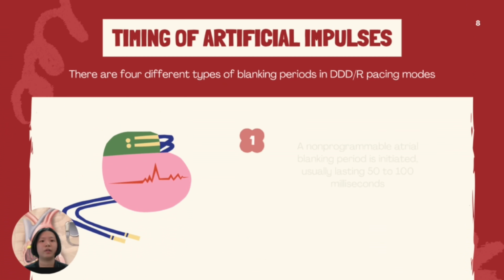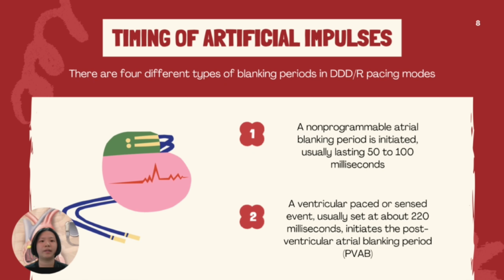There are 4 different types of blanking periods in DDDR pacing modes. Every time the atrium paces or detects, a non-programmable atrial blanking period is initiated, usually lasting 50 to 100 milliseconds. The atrial lead cannot detect its own pacing stimulation or the corresponding P wave during this time. Moreover, a ventricular pace or sense event initiates the post-ventricular atrial blanking period, usually set at about 220 milliseconds. The purpose of this is to stop the atrial lead from detecting far-field ventricular signals like the intrinsic R wave or ventricular pacing output.